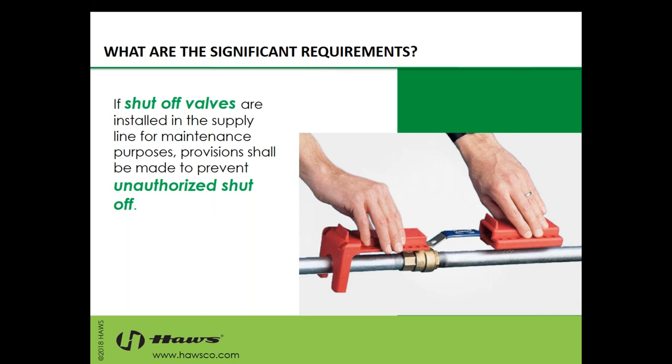It'd be a pretty irresponsible thing to do, but it does happen. We do surveys here at HAWS, a program that I oversee, and every once in a while, the water is shut off to the unit. We have to reactivate, go back to the shower, and finally activate and test it. So this is a big deal. If there's a shutoff valve, make sure that it is locked out to make sure that somebody has access to that water when they reach the equipment.